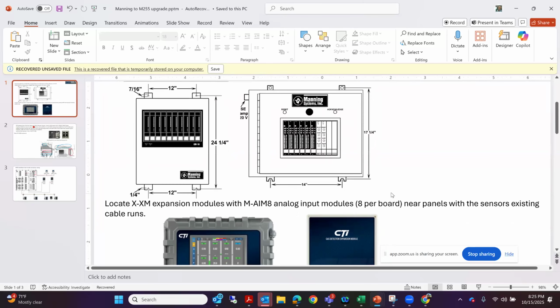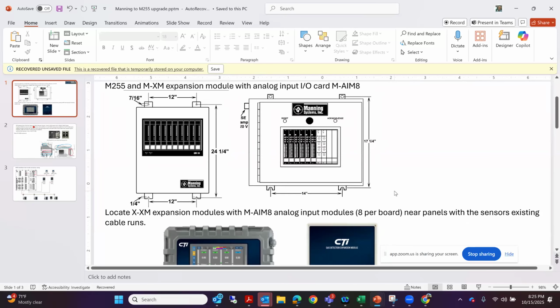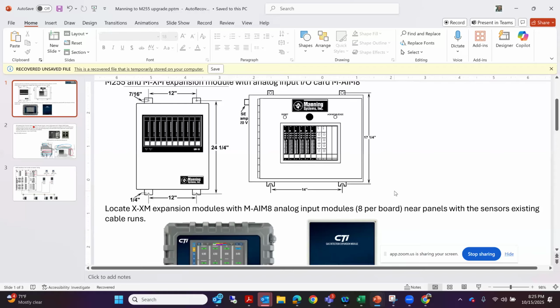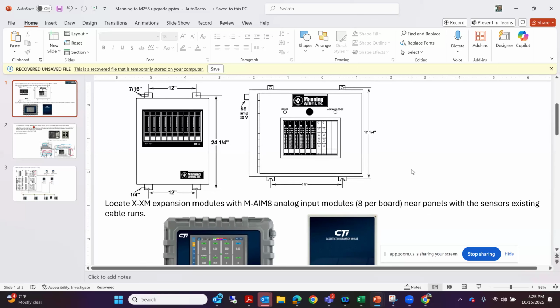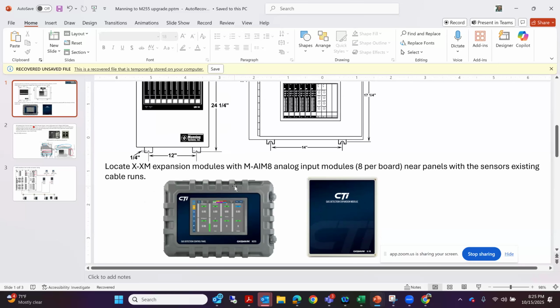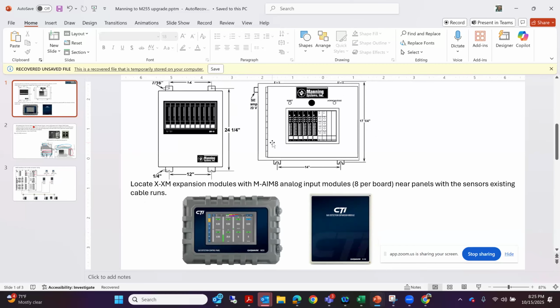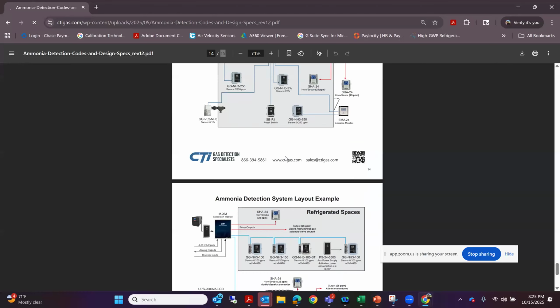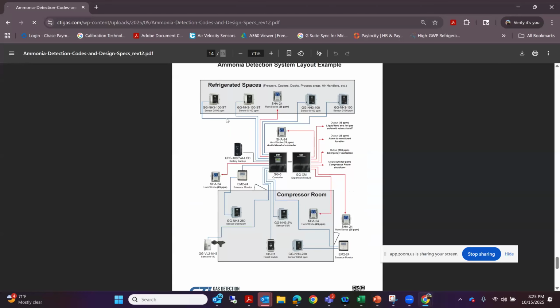I know it's a little harder to restart those systems sometimes, but if they're ready for it, it can be done fairly quickly if there's not a lot of food processing going on there. A lot of the guys, when they're ready for it, can get the system restarted fairly quickly. These older systems are just like our old system here. All these sensors, you had to take a Belden cable, 8770 or 3-conductor shield, and pull every single sensor back to these systems from every single point.